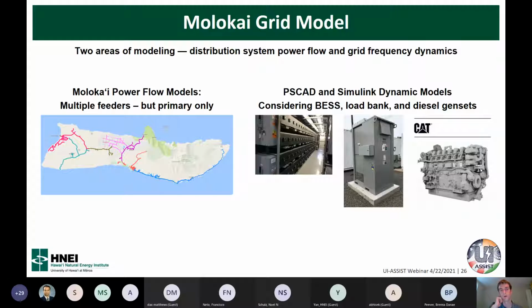But I wanted to bring up another possibility we'll be working on, at least outside UI Assist, or continuing to do outside it: rather than looking at power flow systems and RMS type models, we can look further into the frequency dynamics on that island. It's pretty interesting because it's a low inertia grid with a reasonable amount of PV and load changing, and the diesel gensets are trying to regulate frequency, but meanwhile the PV is taking a larger and larger role, and we have the battery that's also trying to regulate frequency, so there's a lot of interplay there.